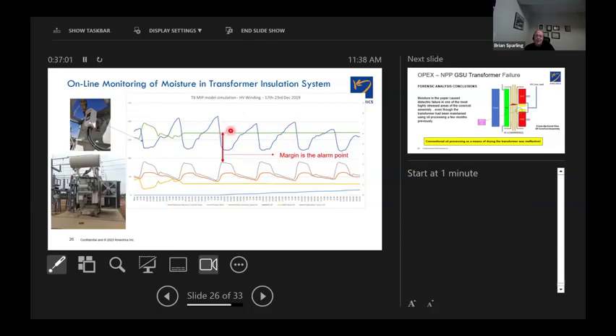So what we compute then is the point at which we've taken into account the equilibrium time, and we look at the margin between the maximum winding hotspot temperature and the temperature at which bubbling is predicted to occur. That's the margin. The margin is the alarm point. As the paper gets wetter, this value is going to come down. When the margin reaches 20 degrees C, the alarm goes and says, hey, stop, reduce load, do what you have to do. But if you don't reduce load, you're going to reach a point of no return in terms of bubbling and shorting out the transformer.